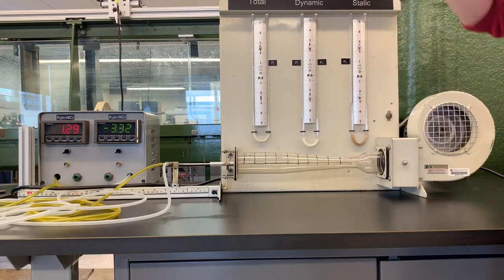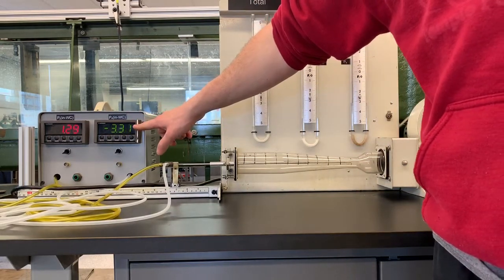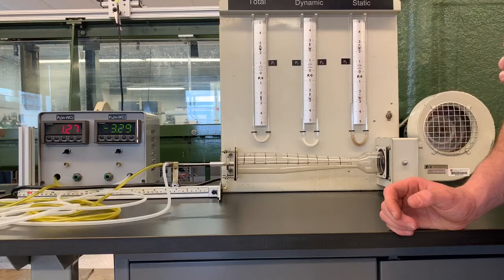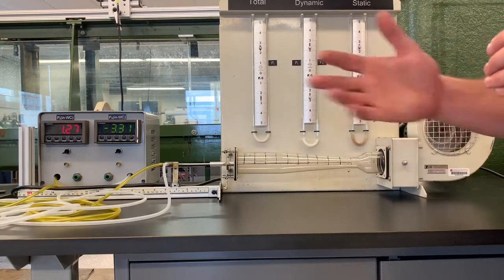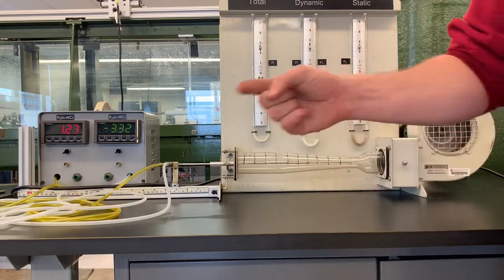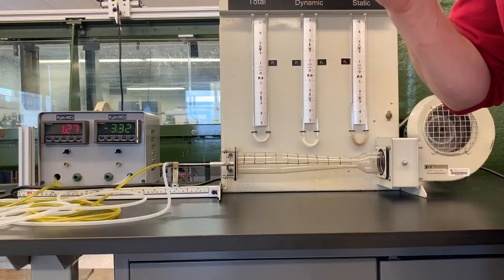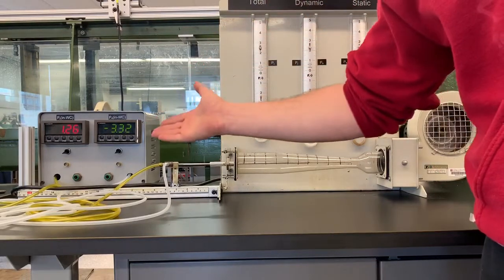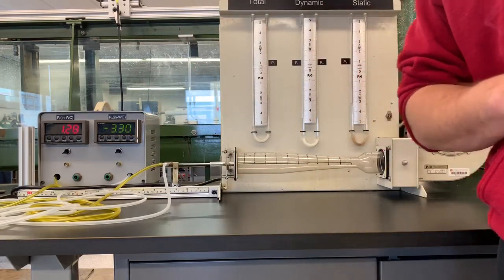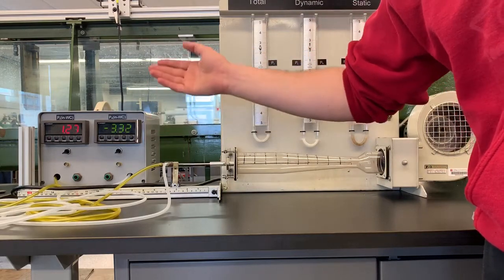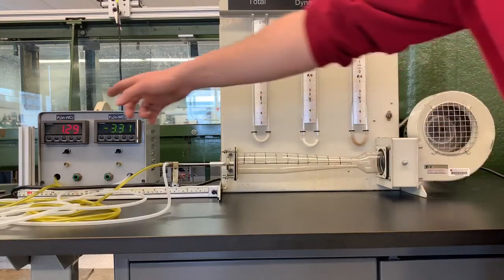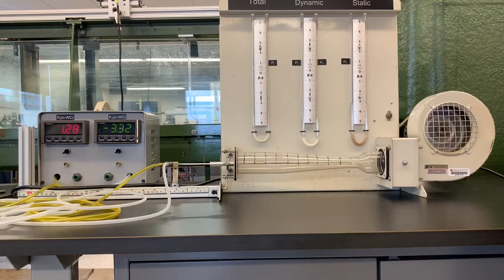Okay, and it's interesting to see how the static pressure has a negative value. Now, static pressure, as you know, the cross-section of the hole for the static pressure probe point is perpendicular to the flow. So, basically in airflow, that static pressure is below your atmospheric pressure value. Realistically, you never really have a negative value of pressure. Pressure could only get to 0. But since we're comparing this to your atmospheric pressure, it is below your atmospheric pressure. Now, your total is still positive, so that is greater than atmospheric pressure.